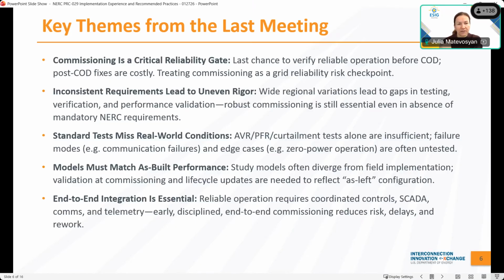Just doing a set of standard tests misses real world conditions. So just doing regular AVR and PFR/curtailment tests that are normally required is maybe insufficient, and you need to test failure modes, for example, communication failures, or some edge cases, for example, providing reactive power at zero power operation, to just ensure that the plant works as intended. And it often gives some insights to even plant developers and plant owners, to understand if something has gone wrong or been done wrong during plant design.